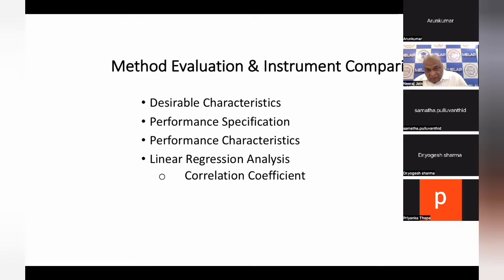Suppose you are saying we need an equipment of 100 tests per hour. In this, precision for hemoglobin shall not be more than 2%. Linearity for hemoglobin shall be up to 25. There shall not be any carryover. These are your desires for that equipment. What all are the company people providing you? Those are performance specifications. They are saying we have one equipment of 75 tests per hour, another equipment of 150 tests per hour. In this, you will get, say, precision of 1.5% for hemoglobin, linearity up to 22, and there will not be any carryover. So this is what they are providing you.